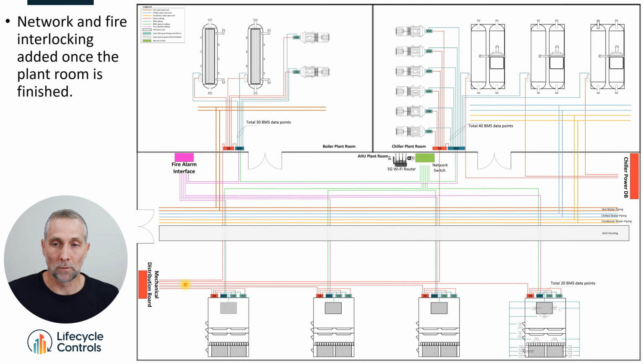So you've still got some work to do. You've got to distribute the network throughout the plant room, the fire interlocking through the plant room, and that last bit of power. But your install's like 80% done. Your commissioning is 80% done. You are miles ahead of where you would have been doing the traditional way.